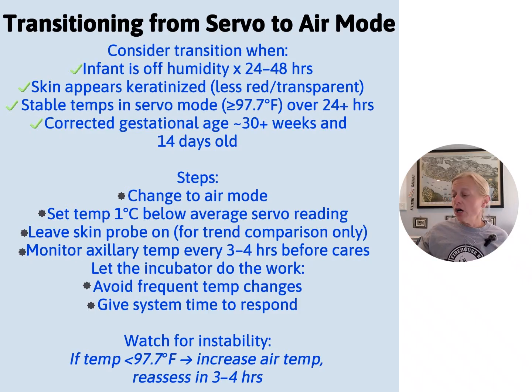If you're still taking care of a smaller baby, it's okay to leave them on there. But if you're 31 weeks, 1,400 grams, we want to kind of normalize some of this, go ahead and transition them out of there. You're going to change to air mode. You're going to get it below this servo reading because you're probably going to be dressing them or using a more intense positioning device such as this. And if we're doing that, we don't need as warm of an incubator. You can leave the temp probe on even just for tracking and trending to make sure the baby's not getting too hot or too cold.